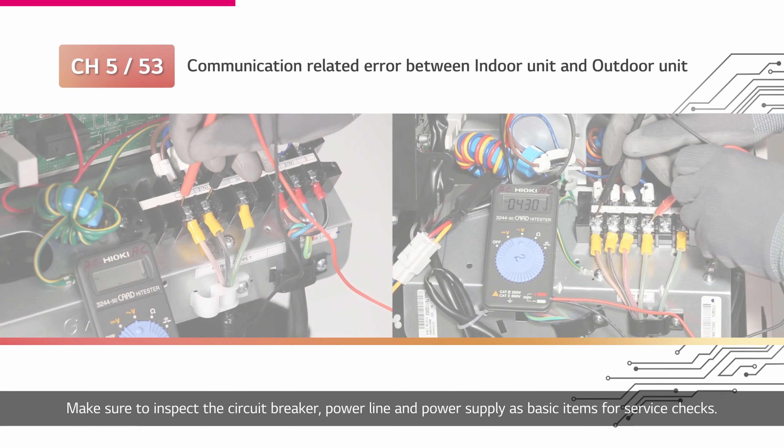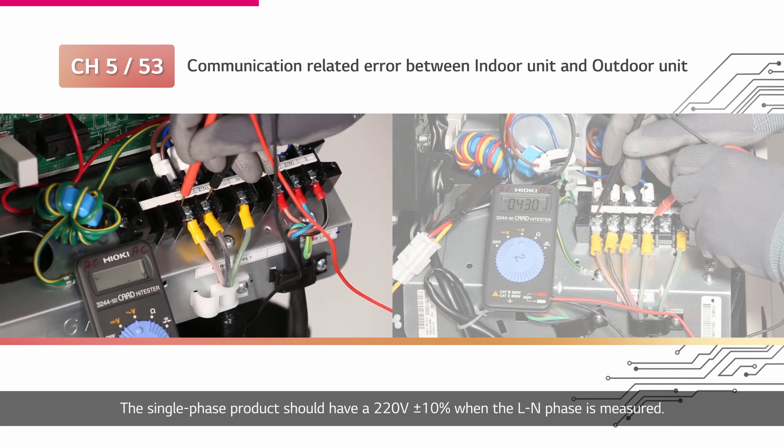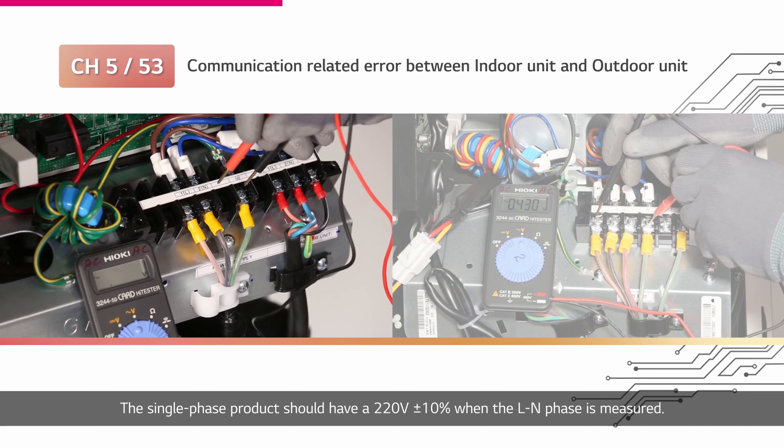Make sure to inspect the circuit breaker, power line, and power supply as basic items for service checks. The single phase product should have 220V plus minus 10% when the LN phase is measured.